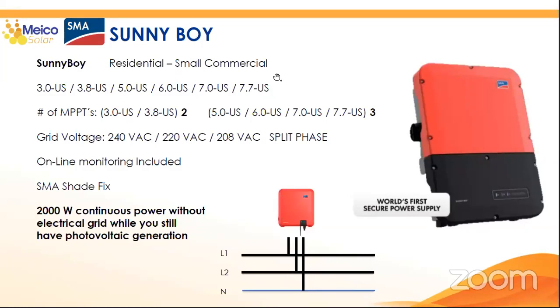Let's go now with the Sunny Boy inverters. These are string inverters, also for residential and small commercial projects. The US versions have powers from 3 to 7.7 kilowatts. This is very important: you have two MPPTs in the 3.0 kilowatt and 3.8 kilowatt versions, but three MPPTs in the versions from 5 kilowatt to 7.7 kilowatt, which is a lot for a project this small. This also works for whatever voltage you find in the split phase region, from 240 to 208 volts depending on the country. And very important, it has online monitoring included.